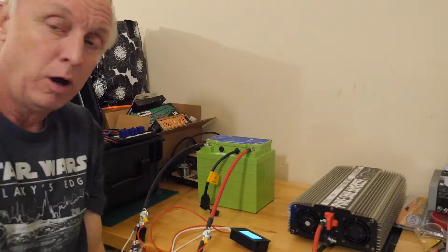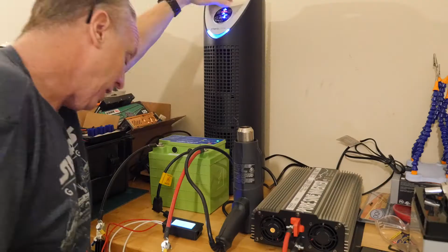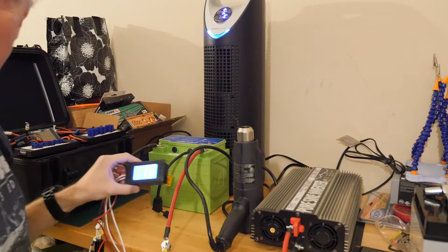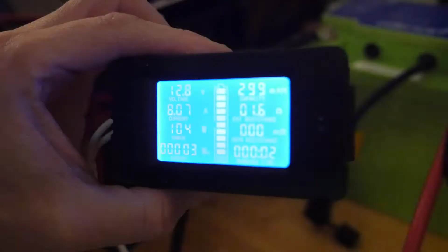Alright, I'm going to do a capacity test on this Valence battery that we just fully charged up. To do that, the discharge rate is 0.2C, which on a 40 amp hour battery would be 8 amps. So I need to hook up some stuff to this power supply or inverter to get this battery up to 8 amps. Let's start doing that right now. Alright, 8 amps, we're exactly at 8 amps. Can you guys see that?